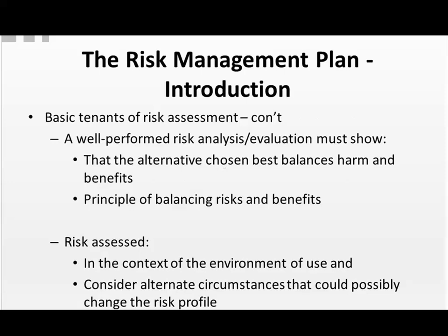Risk is assessed in the context of the environment of use. In other words, literally, where will the device be used and how will it be used in that environment? You should always consider alternate circumstances that could possibly change the risk profile, such as what is the state of clinical practice? Could changes in medical practice increase the risk with this device? What will be the impact of aging of the device later in the life cycle? We're talking about parts wearing out and maintenance that's required.